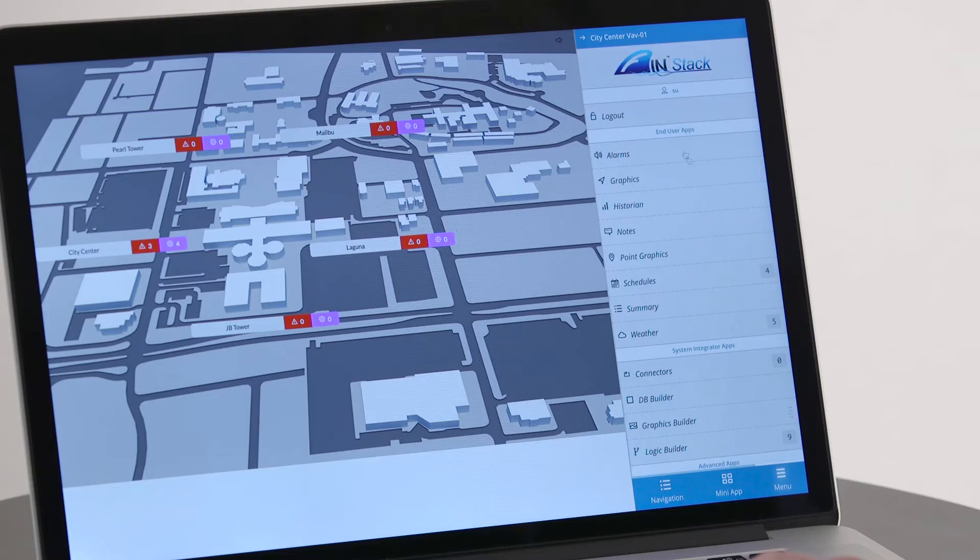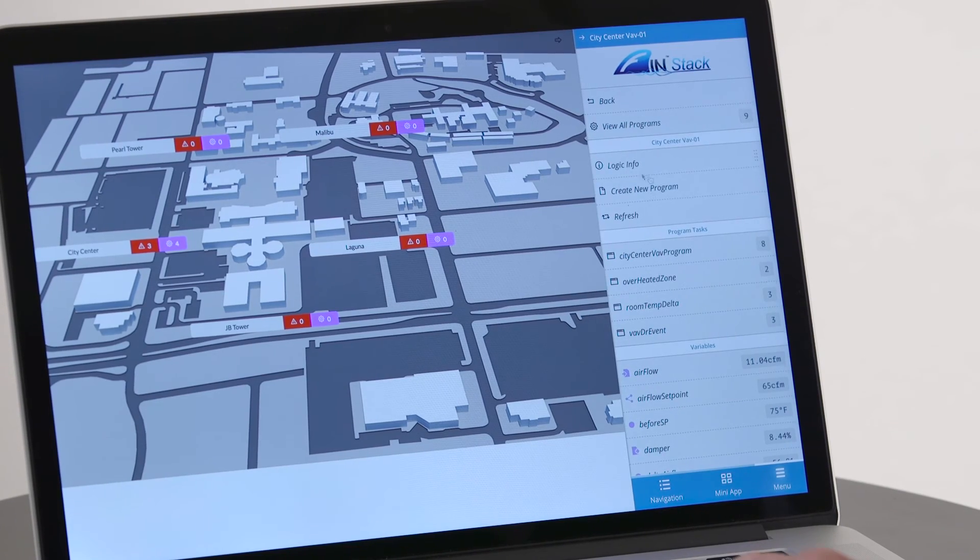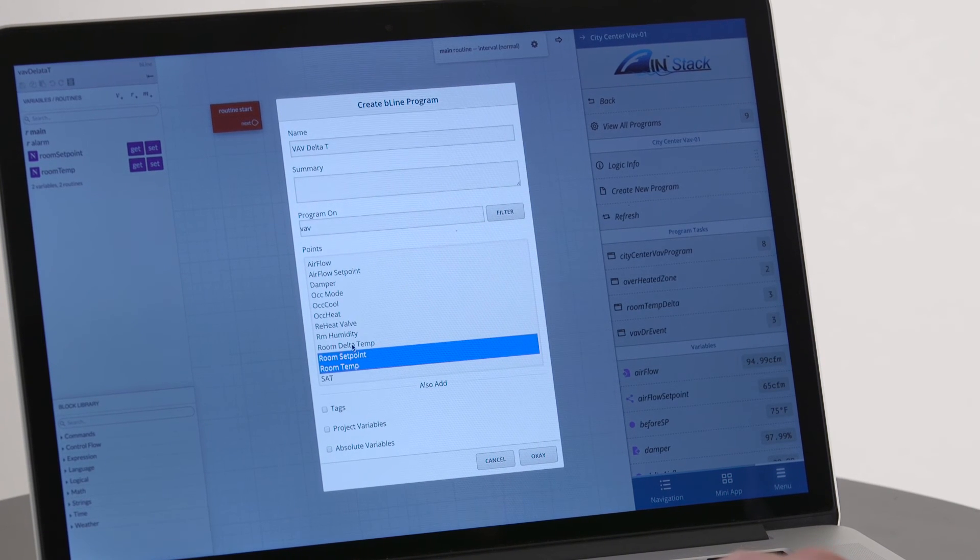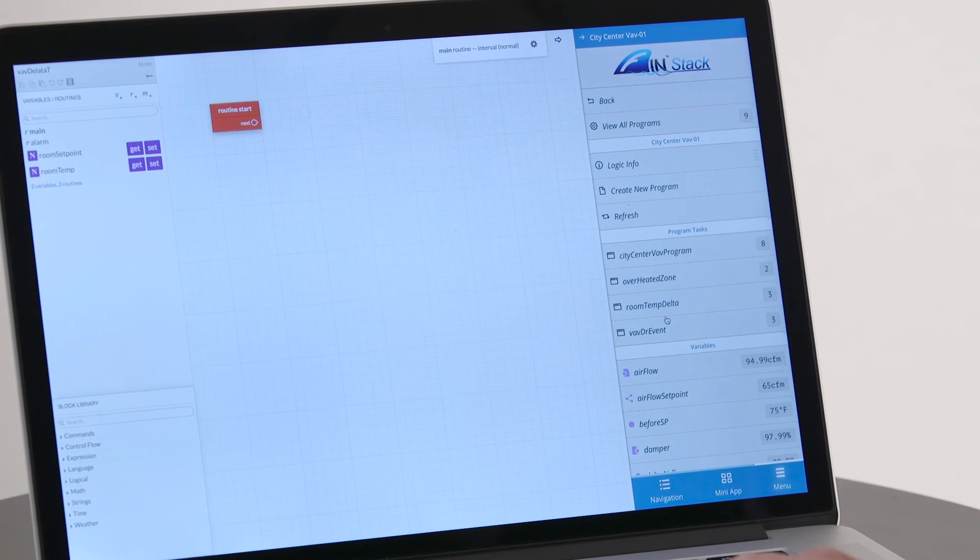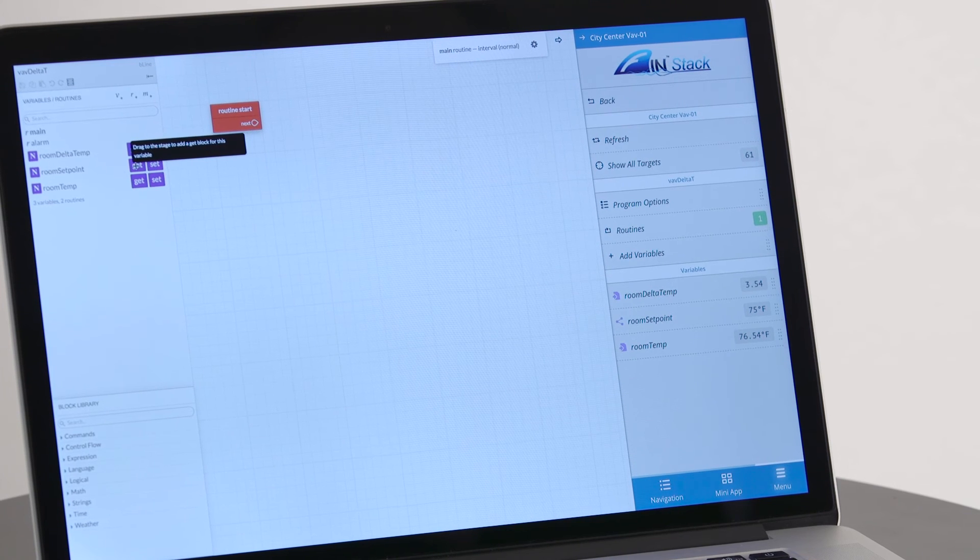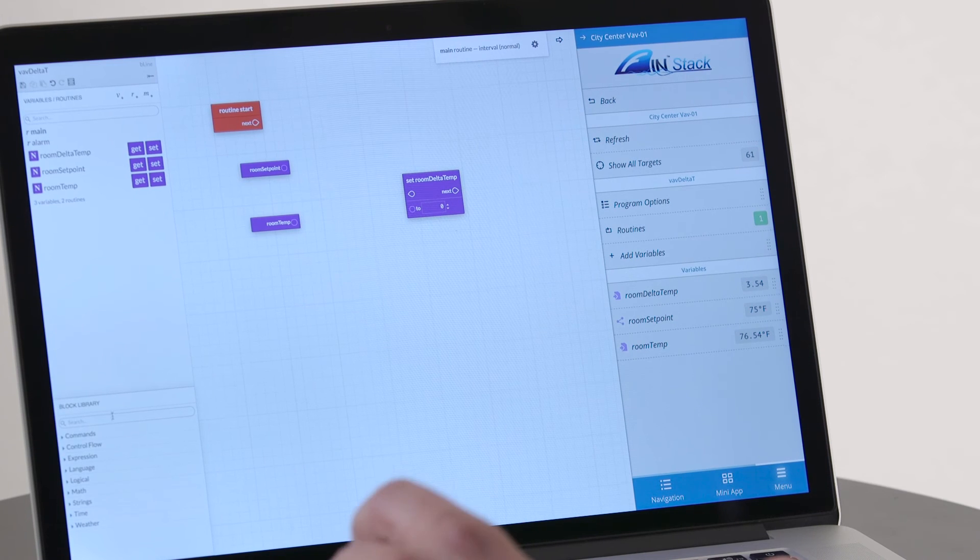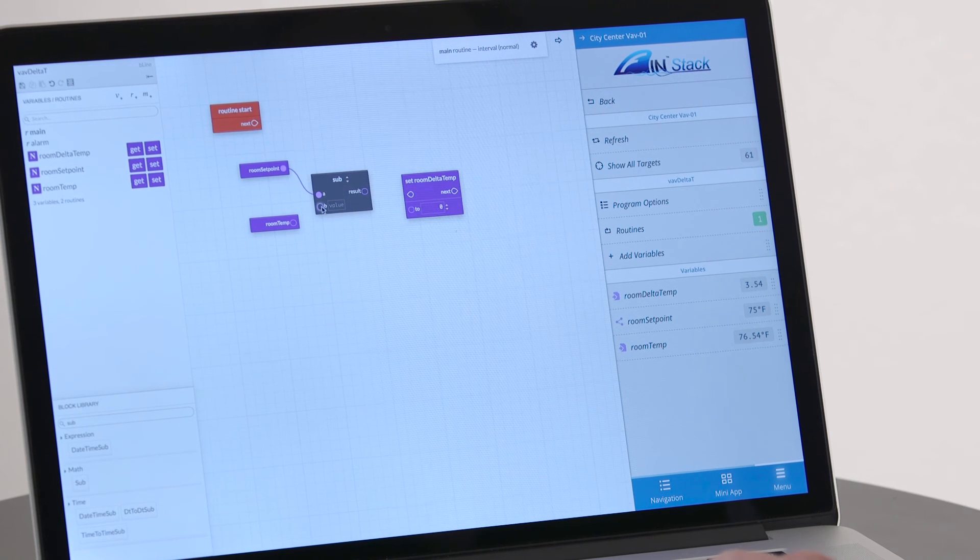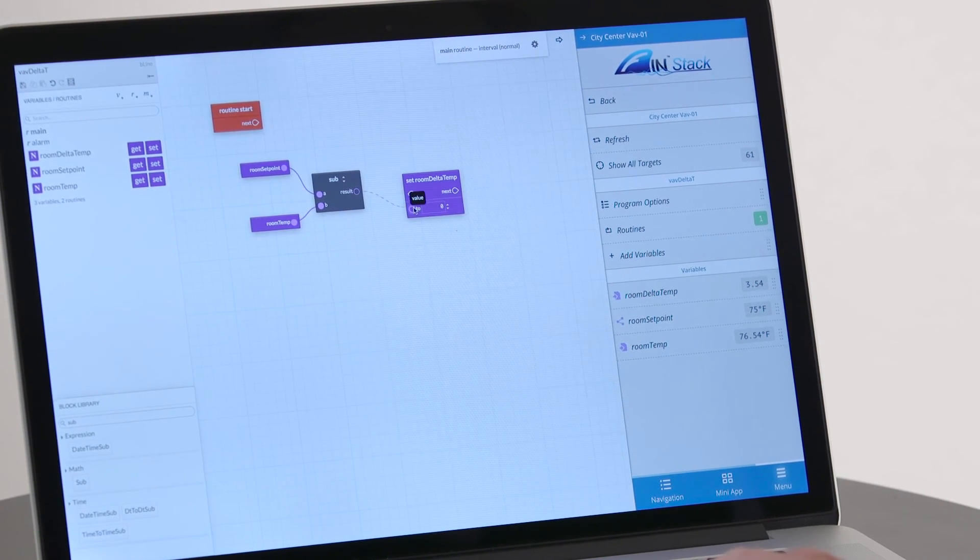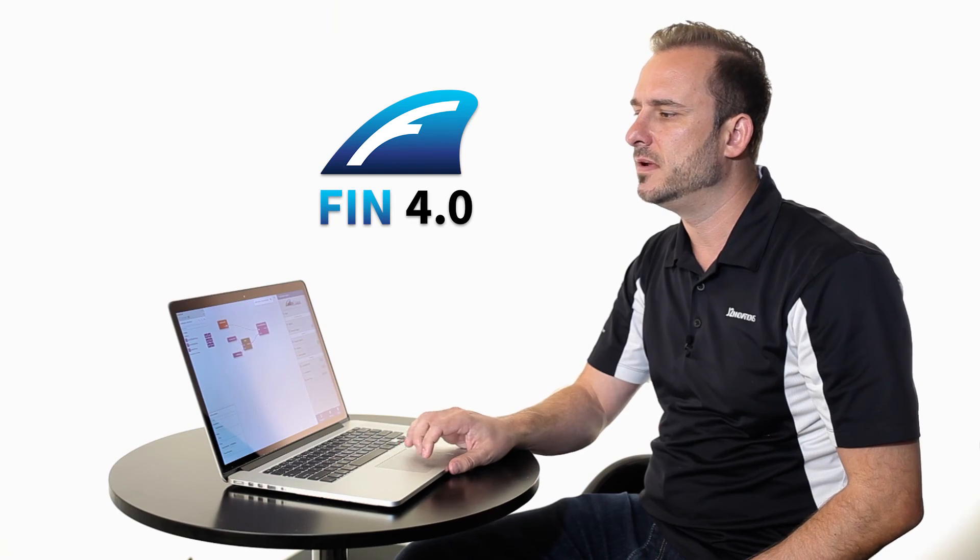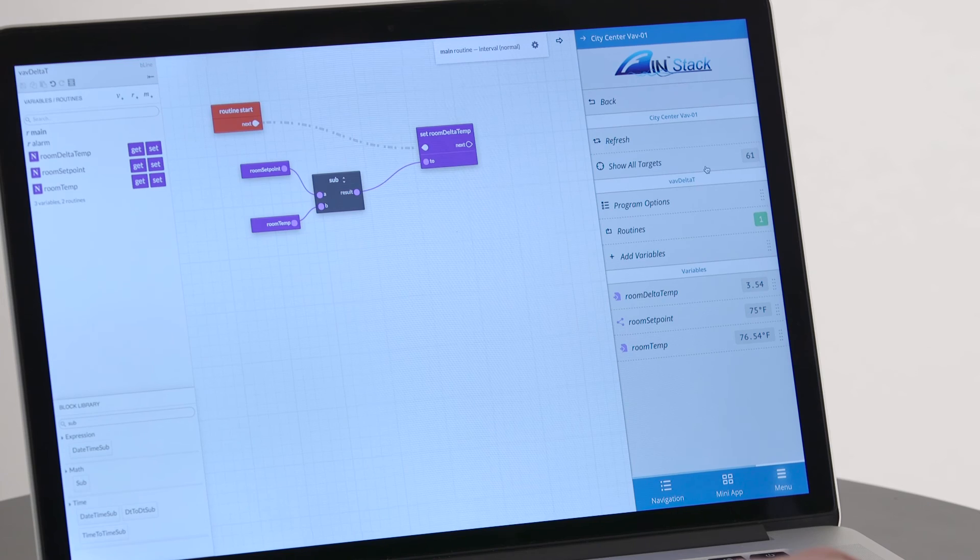You want to get context. So navigate to city center VAV1 and just go into the logic builder, create a new program. So now let's create a VAV Delta T program for every VAV in my database. And let's select the room temperature set point and Delta T. Now what you're seeing is the wire sheet that's running in the browser, no Java plugin, right? 100% in the browser. I'm going to drag my set point and my room temperature and let's get the Delta T. Now let's search for a block and let's find a subtract block. This program that I just created when I hit the save button now runs on every single VAV in your entire enterprise, whether it's one, 61 or a thousand. No more copying, no more linking. You write one program and it runs everywhere using Haystack tags.